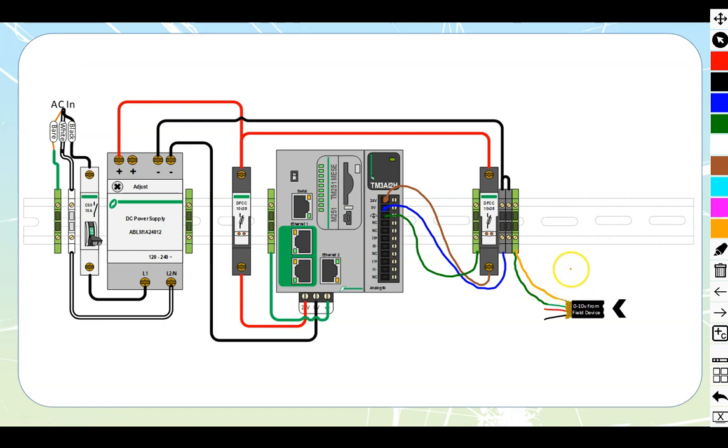First thing we're going to do is start by grounding down this cable. We're going to take my ground in and also take my shield in. Always the shield gets grounded down at the main end. There's multiple ways to do it. There's these little clamps that grab it, or you can strip off and tie stuff in. There's a pile of different methods that you can use for this, but you do want it to be grounded on the source end and isolated on the other end.